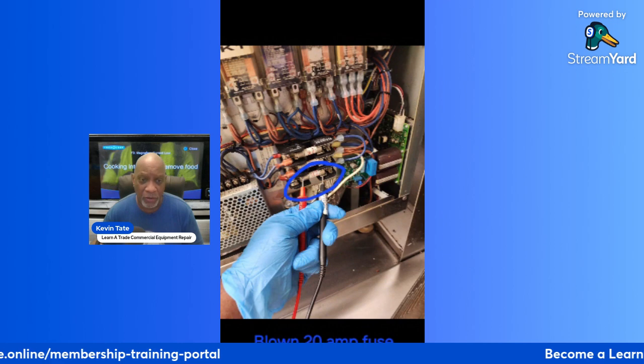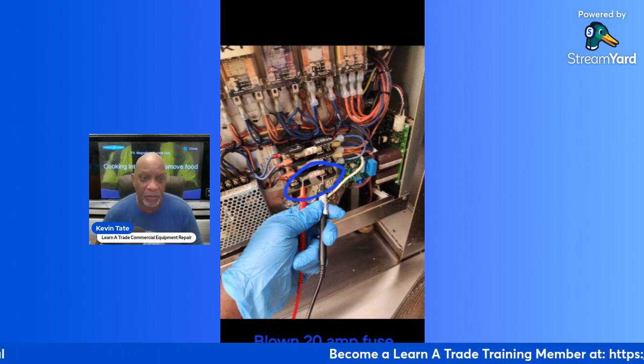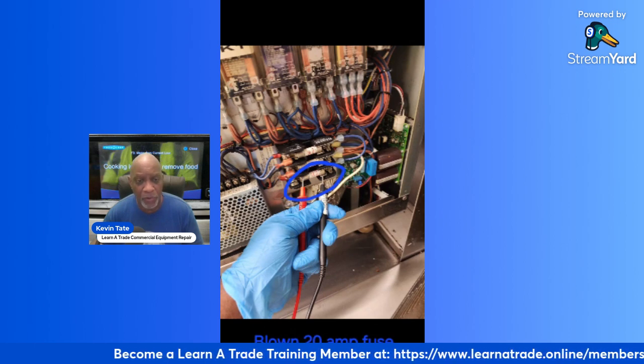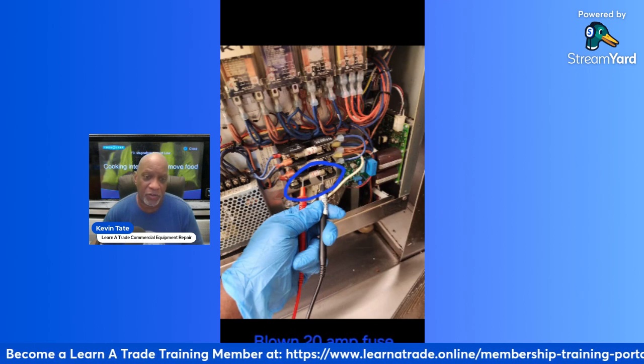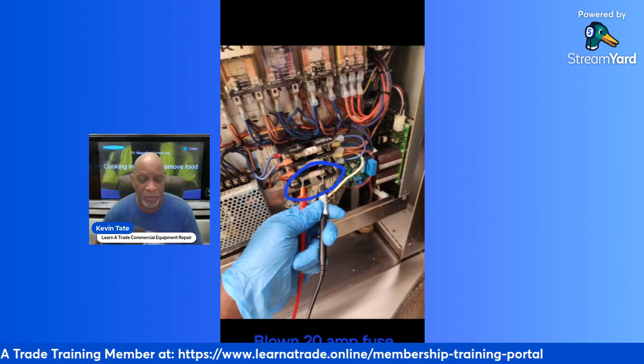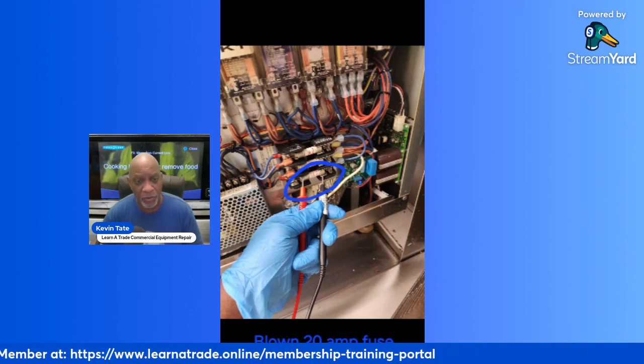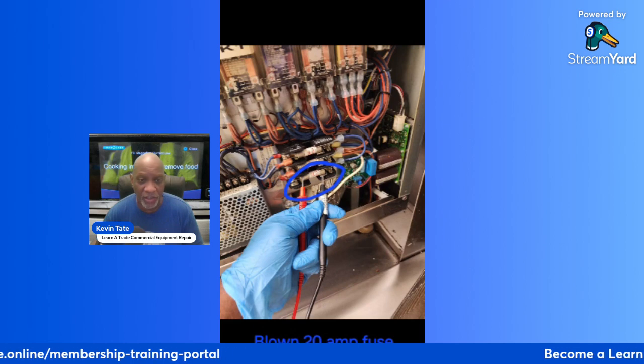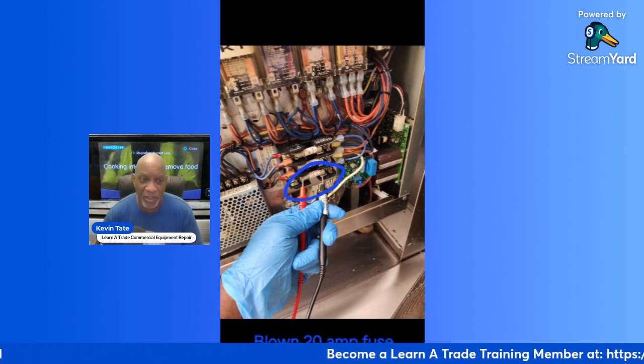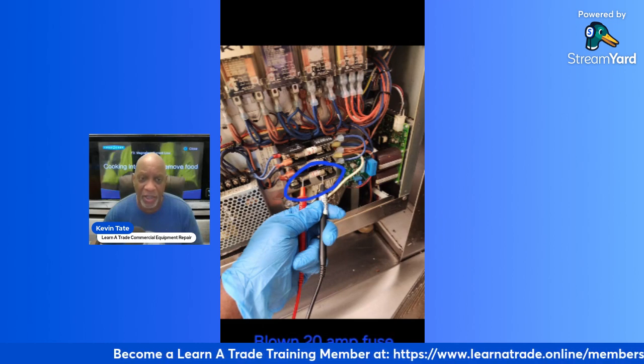And the next step, after you recognize you have a bad K2 relay, is to go down with your ohm meter. The blue circle is indicating the 20 amp fuse, and you want to test that fuse to see if you have continuity. More than likely, you'll have a blown fuse there, and you'll need to replace it.